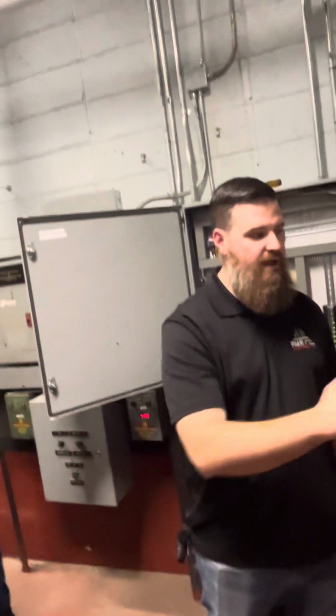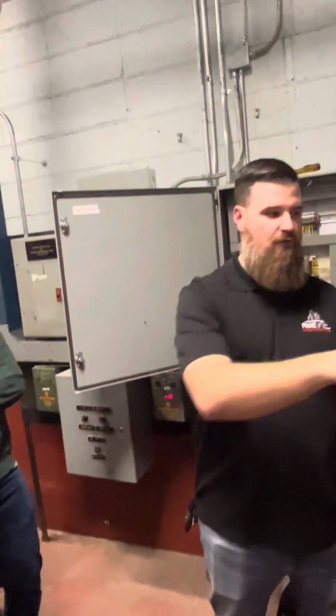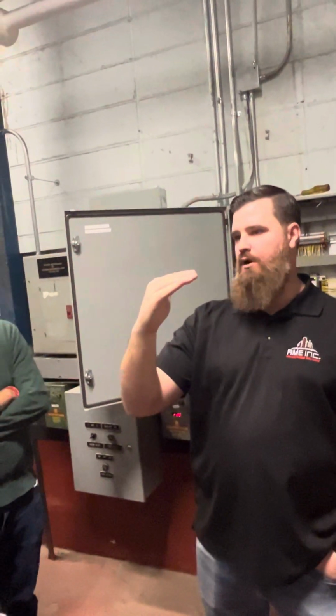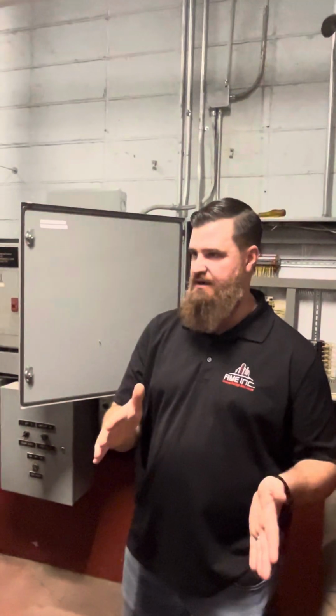Okay? Now, third boiler, lag boiler, stage 3. If we are a half pound or more under set point for 40 minutes, so if we're at 2.5 pounds or less for 40 minutes from the time that we've turned everything on, we're going to kick on stage 3. Okay, but stage 3 is going to turn off the moment we get to 3.2 pounds, because it's a 0.2 differential on that. So if you set it for 4, you're going to add all these values plus or minus from 4 pounds, or if we're at 2 pounds, plus or minus from 2 pounds. So all that makes sense, right?